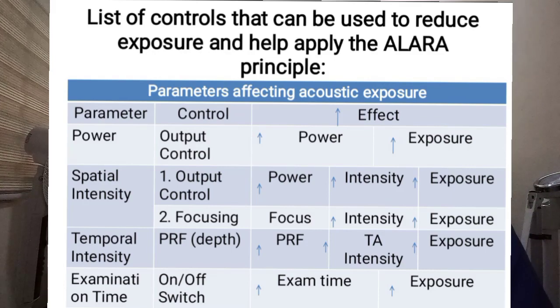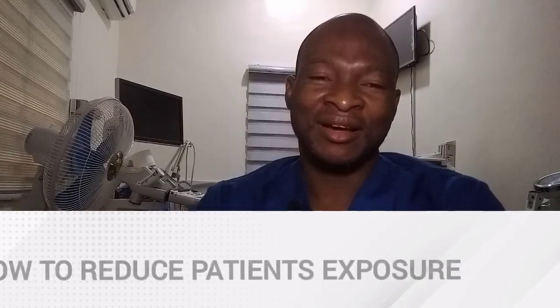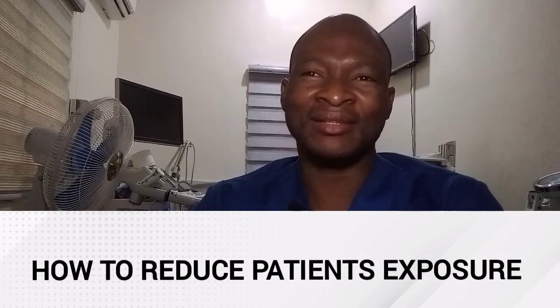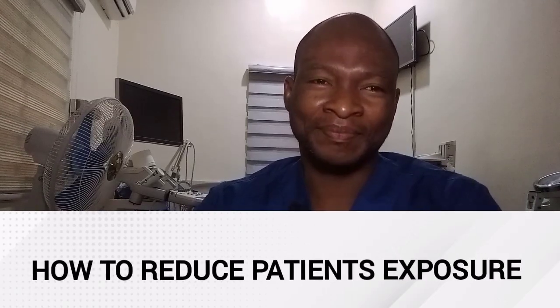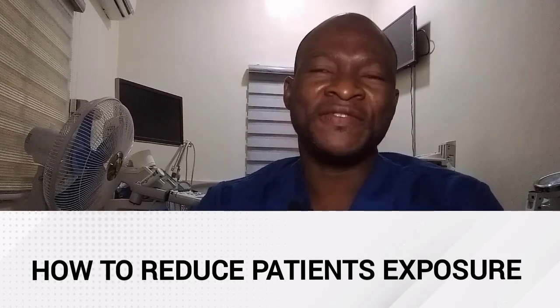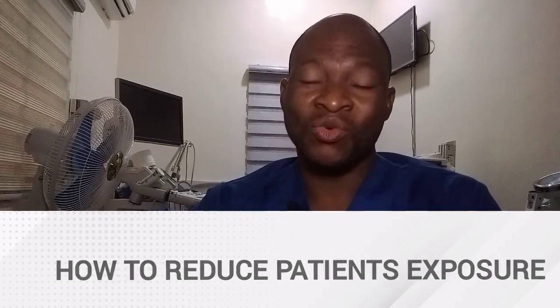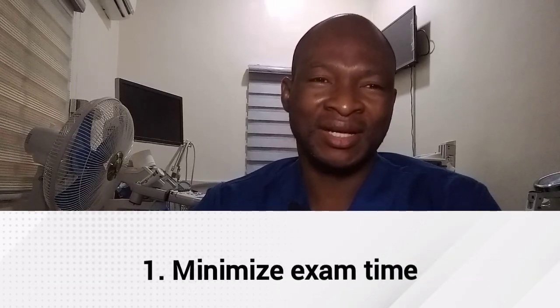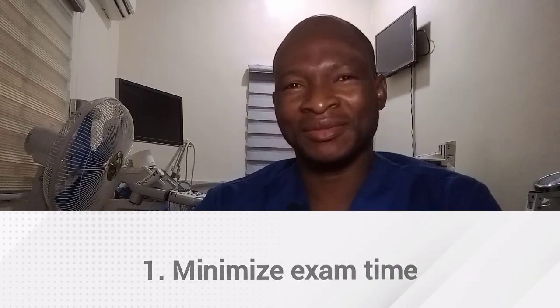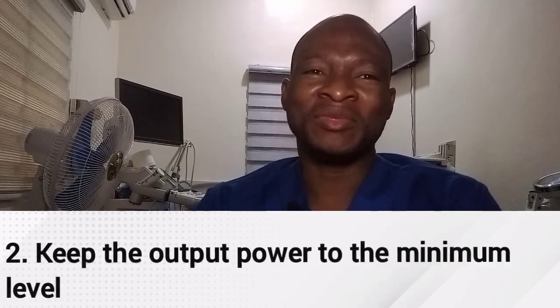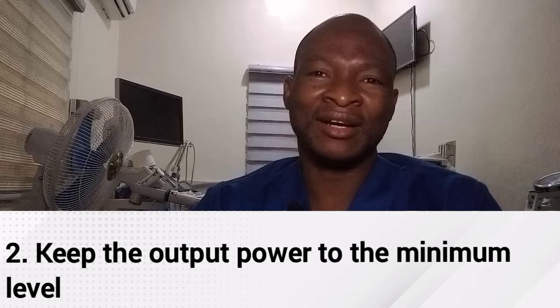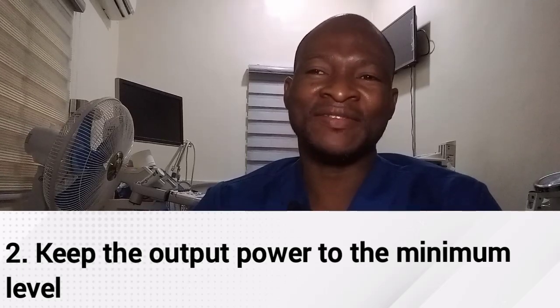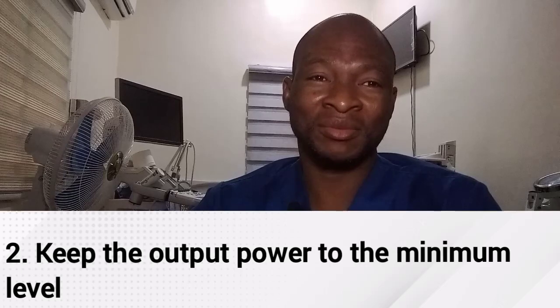Examination time is one of those parameters. So you have the on and off switch. Increased examination time means increased exposure. So how can acoustic exposure to the patient be minimized during the course of an exam? The most effective methods are: number 1, to minimize the examination time as much as possible. Number 2, keep the power at the minimum level required to obtain the necessary diagnostic information. Increasing the receiver gain will help keep power as low as possible.